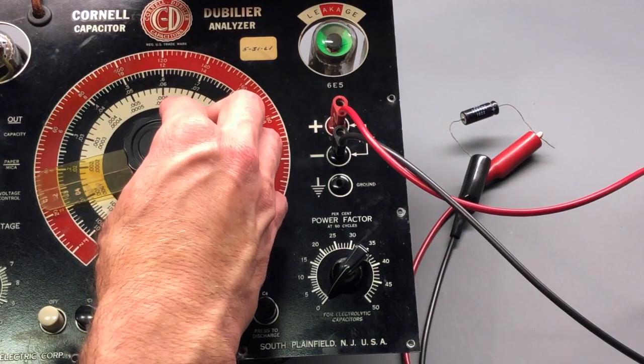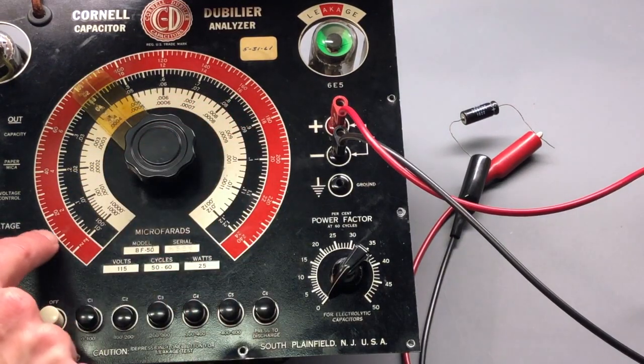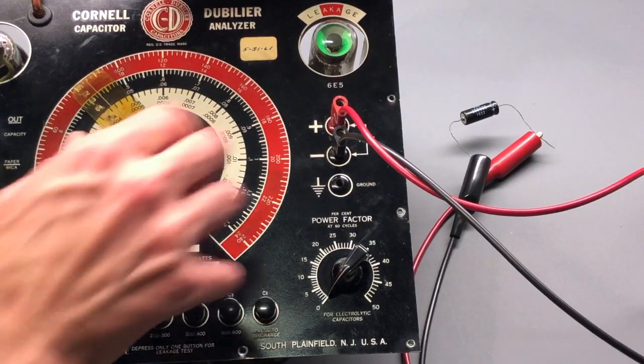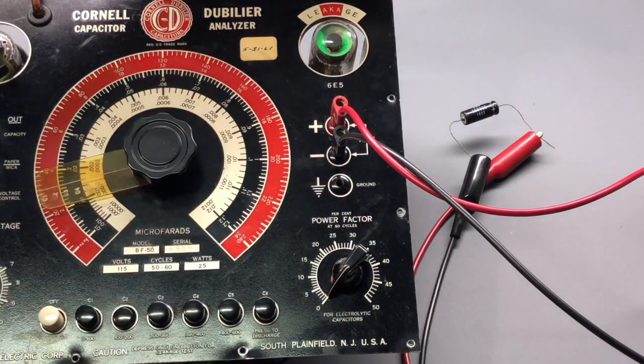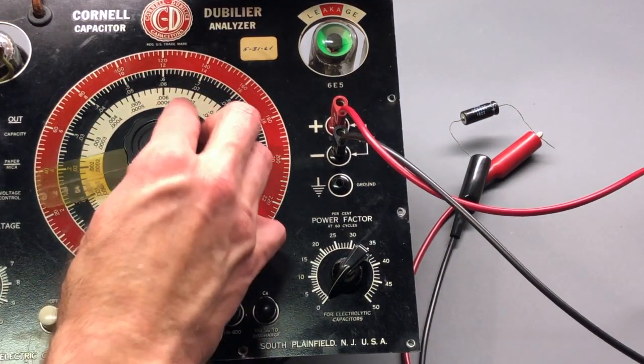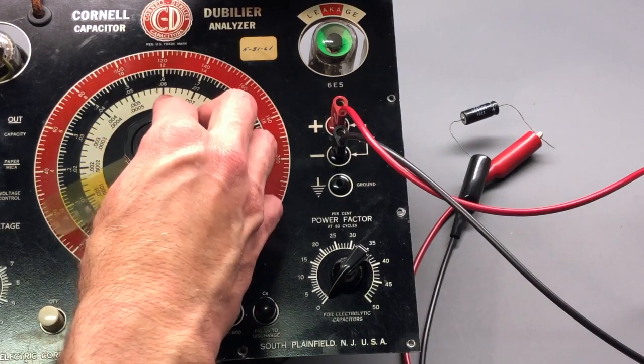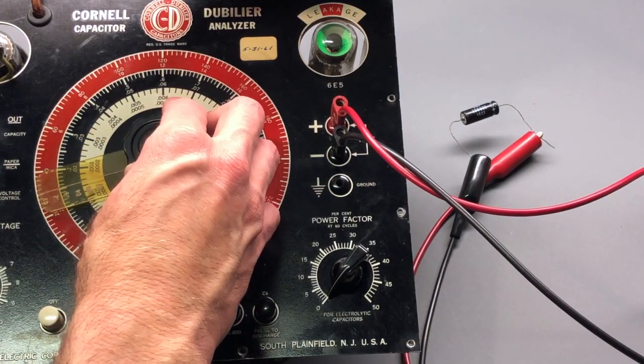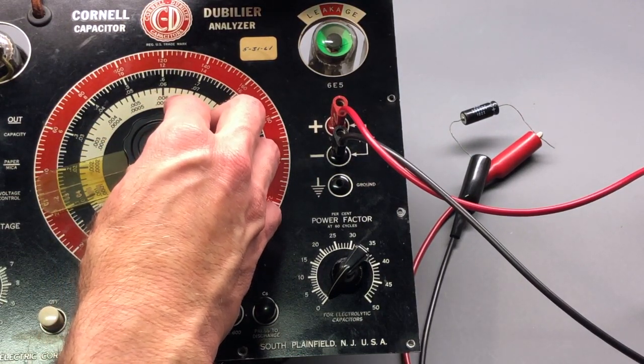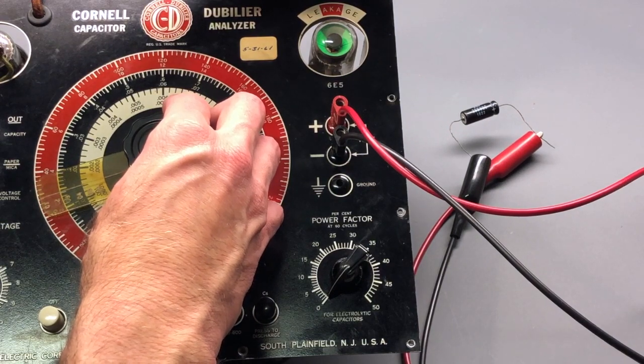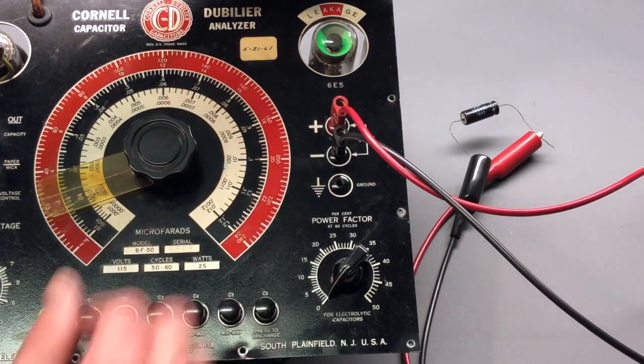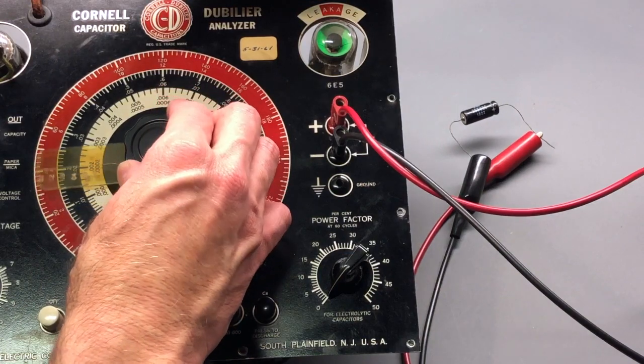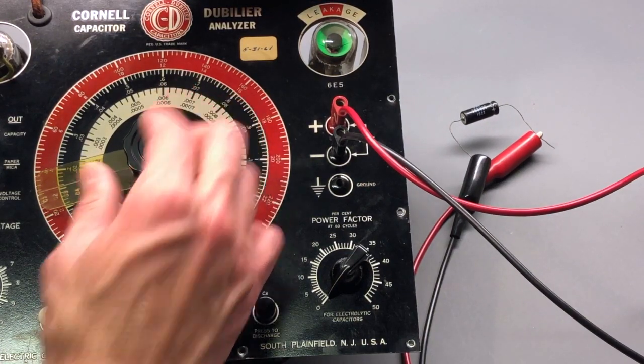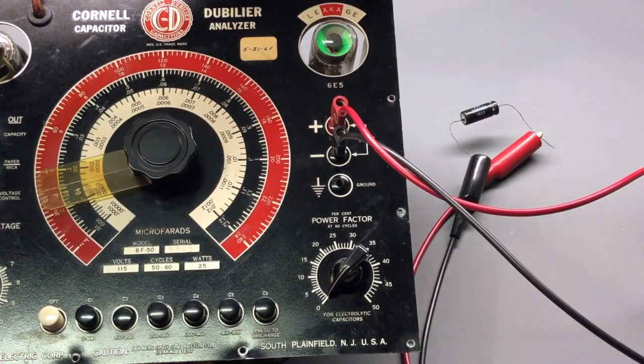So again, we know it's 3 microfarad. That really should be between the 2 and the 4 right there. So there is no activity happening whatsoever on the eye tube in this capacity test. So we know the eye tube functions because it was working just fine for the leakage test, but no response whatsoever on this test. So it does appear that there is a problem.